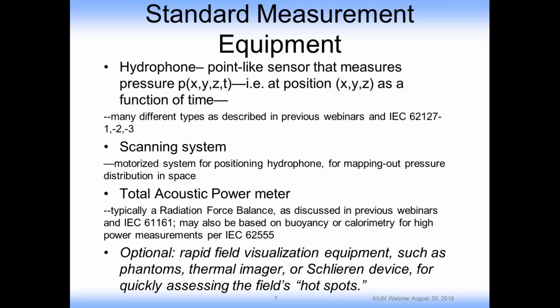I will mention that there's an optional piece of equipment for rapid visualization of the field, particularly in the therapeutic realm. There's often concern about not just the place in the ultrasound field that gives the maximum output, but secondary maxima, which may be far away from features of the field such as side lobes. In these new standards, there is concern about those side lobes and a requirement to measure them, given that they can be far away from the beam axis. There is sometimes a desire to first identify their location by doing a rapid, even if qualitative, scan of the field, and follow that up with hydrophone measurements. And typical equipment for this are thermal imagers, phantoms, or Schlieren devices.